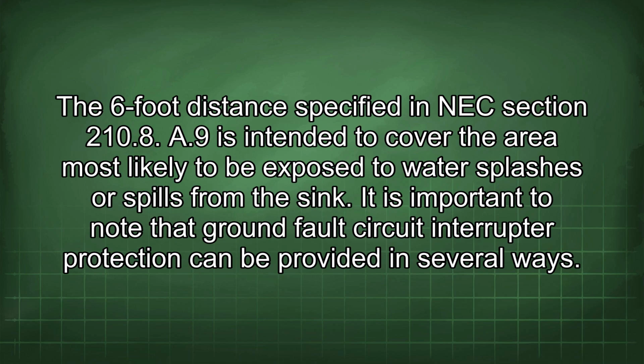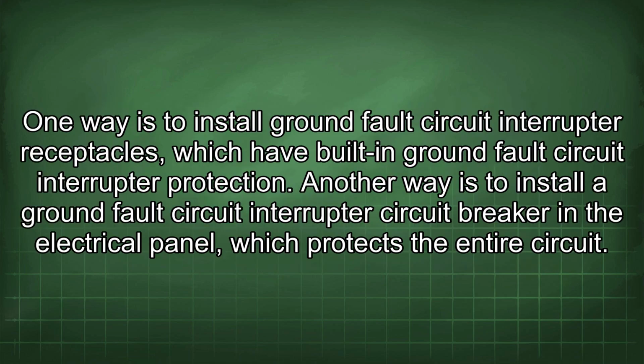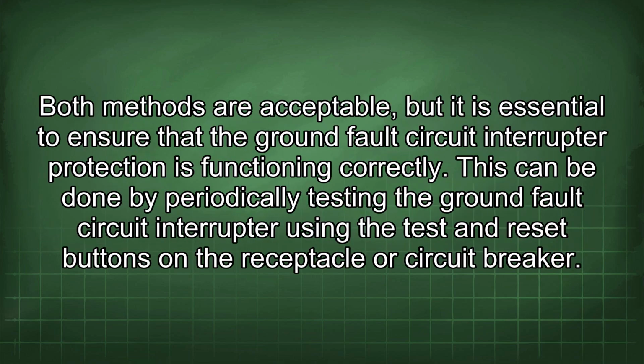It is important to note that ground fault circuit interrupter protection can be provided in several ways. One way is to install ground fault circuit interrupter receptacles, which have built-in ground fault circuit interrupter protection. Another way is to install a ground fault circuit interrupter circuit breaker in the electrical panel, which protects the entire circuit. Both methods are acceptable, but it is essential to ensure that the protection is functioning correctly. This can be done by periodically testing the ground fault circuit interrupter using the test and reset buttons on the receptacle or circuit breaker.